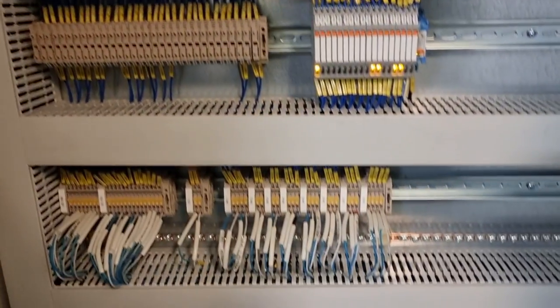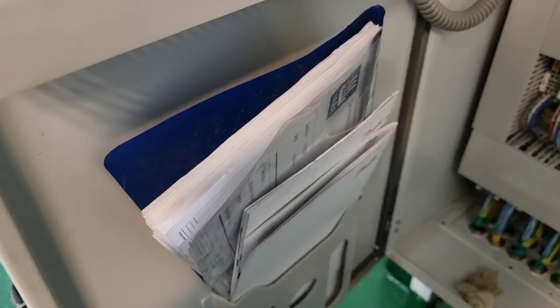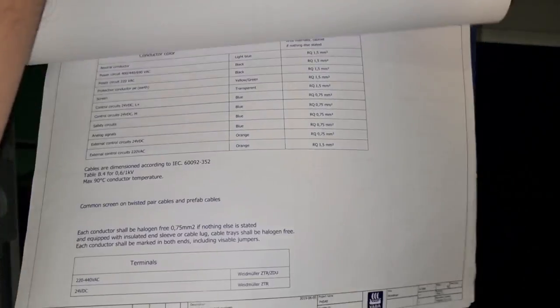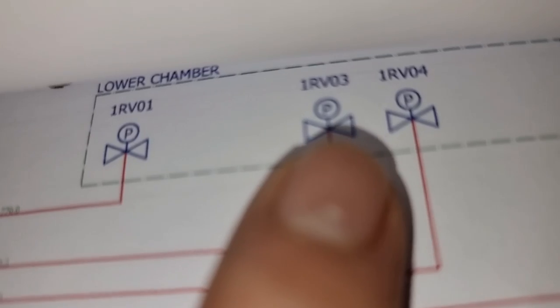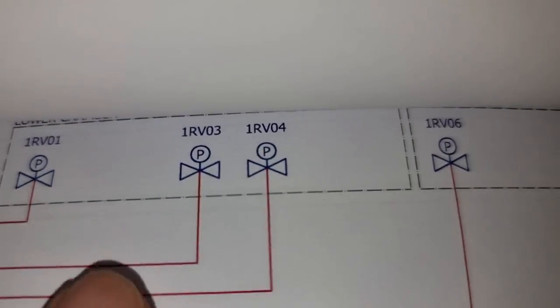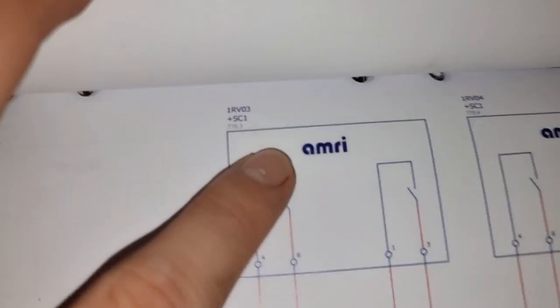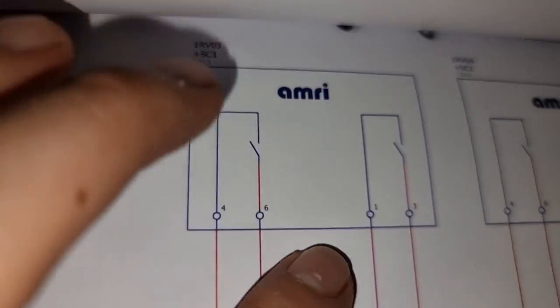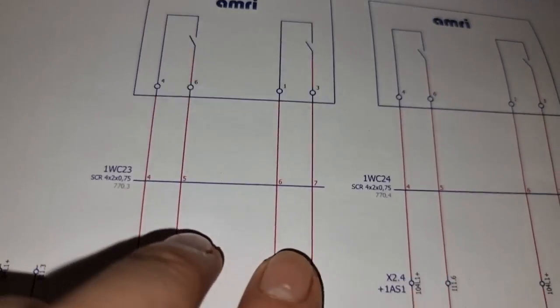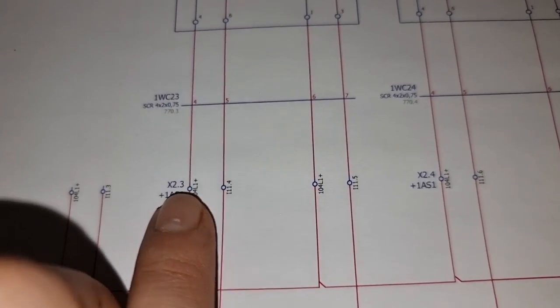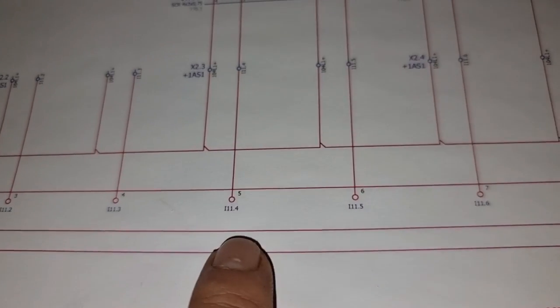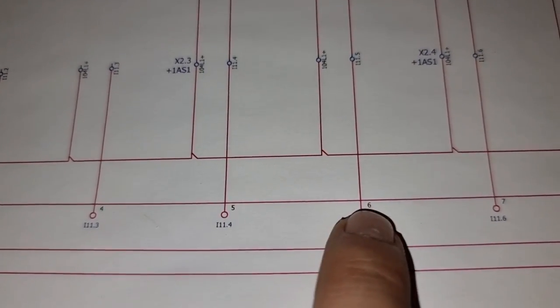and check what controls this valve. So of course, we need to consult our wiring diagram, and good thing that the wiring diagram is already on the cabinet. So checking the wiring diagram, I focus only on this specific valve. And looking at the wiring diagram, we have two separate pages for the indication, which are these limit switches or the micro switches, which are connected to one of the input-output modules on our controller.